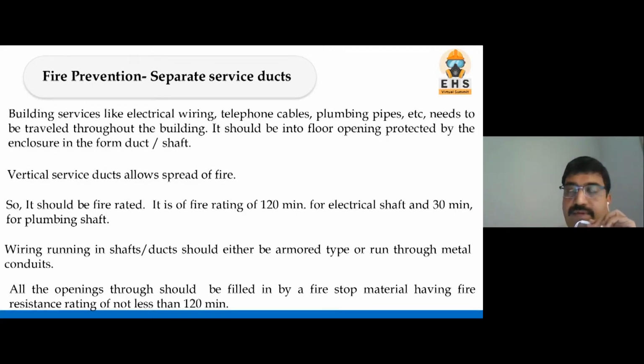But now what happened? This vertical shaft again allows the fire to spread, because fire always spreads vertically. So if the shaft is there and proper care is not taken, then that is a way for fire to spread. So it is very clearly mentioned that if it's an electrical shaft, the fire rating should be 120. For other shafts, it may be 30 minutes.